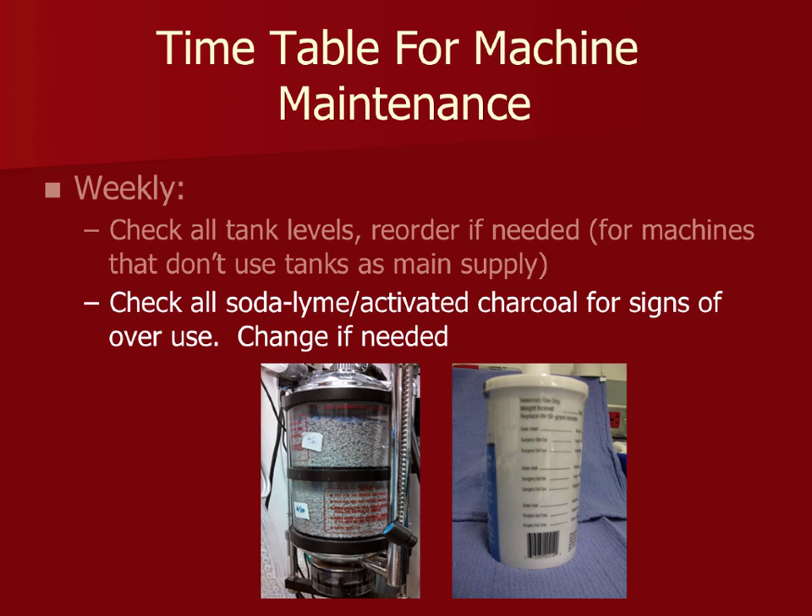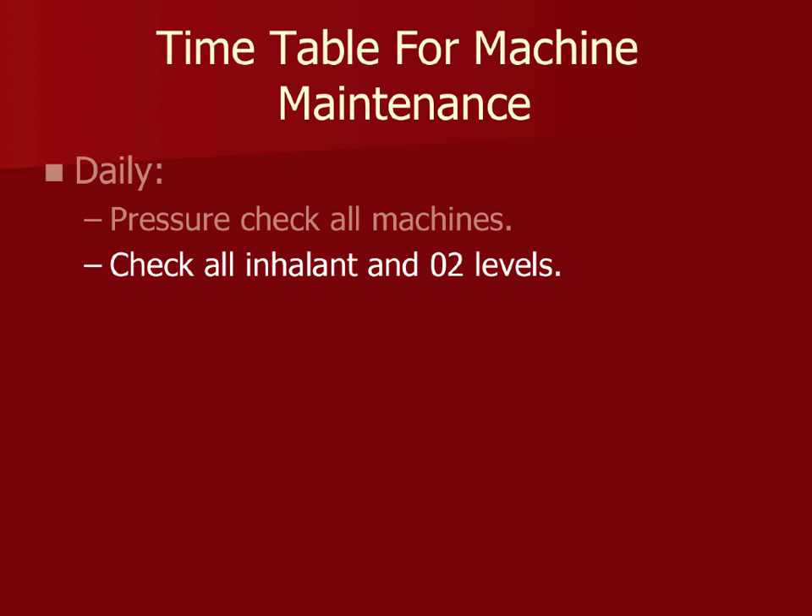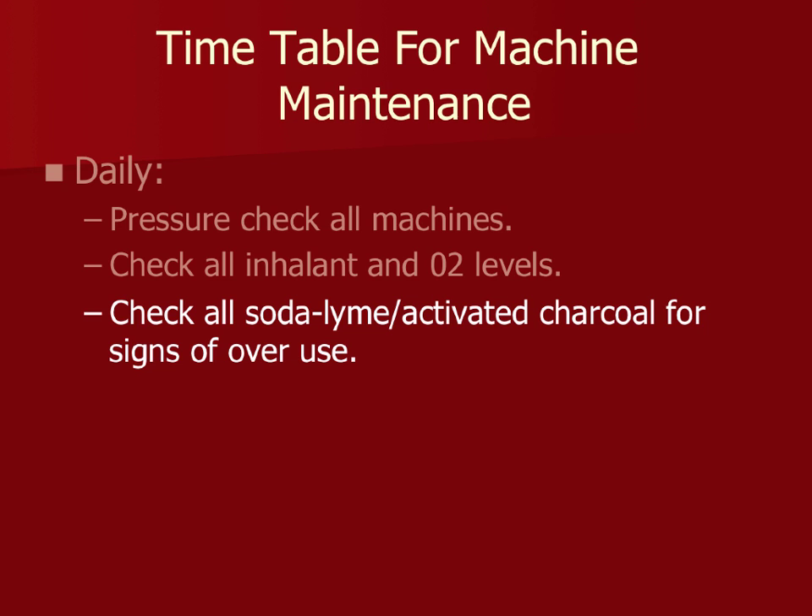Daily: check your machines each and every time they are used. Make sure ISO levels are adequate, that any fill port is properly closed off so there are no leaks. Check your inhalant levels, oxygen levels, tank pressure, and make sure soda lime isn't becoming purple or running low. Check your activated charcoal canisters. We have our students use a checklist for every single case — I can't stress enough the importance of checking your machine every time it is used.